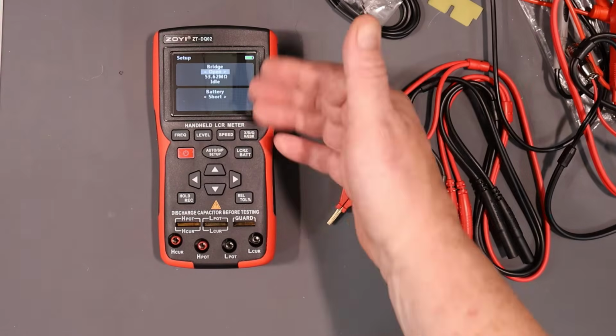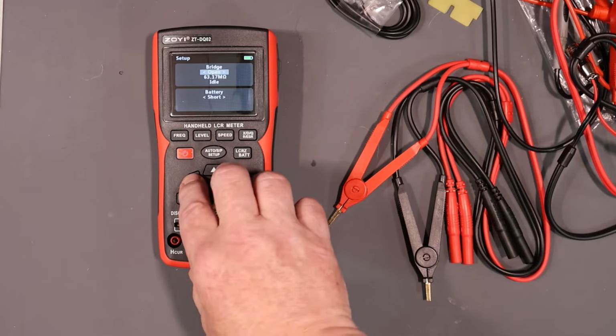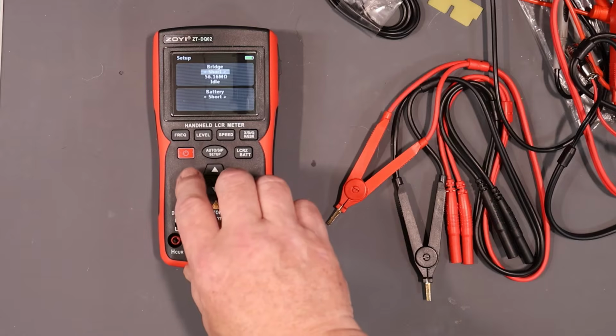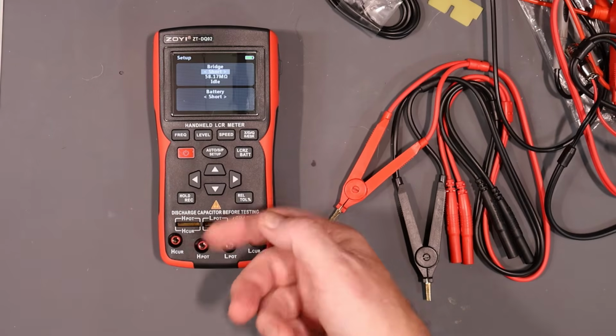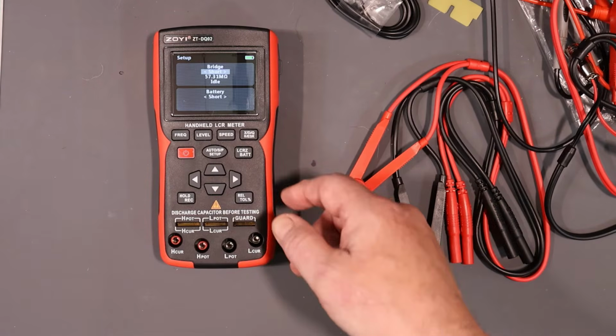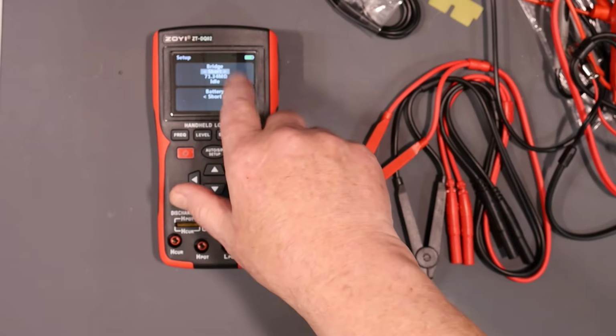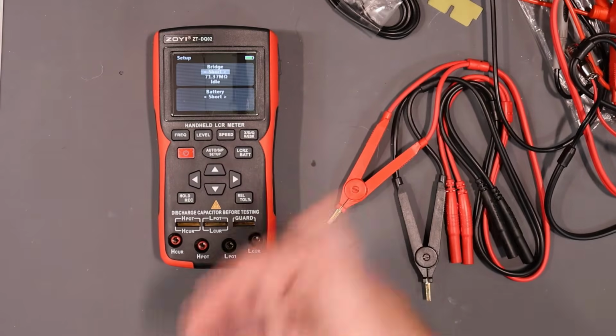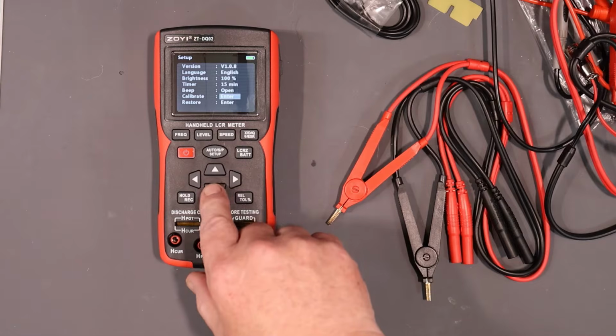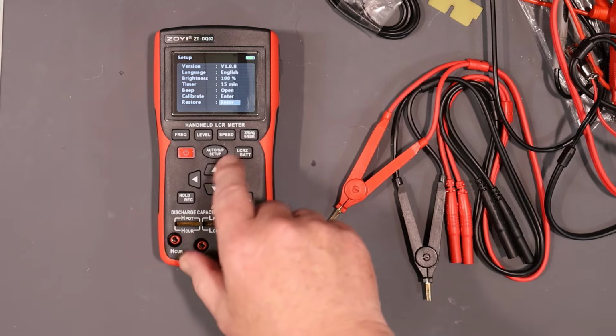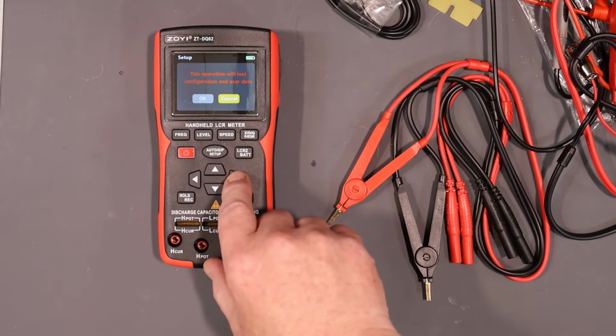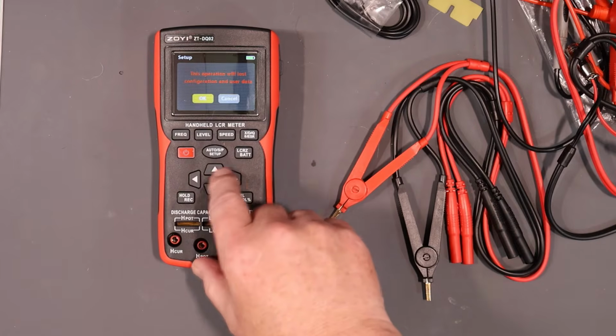As for me, I'm just going to run with the factory calibrations, other than the open and short calibrations, which I'll do when I change my measurement type. Now, if you go in there and start messing around with the calibration and find things aren't working properly anymore, go down here to factory restore and go into that. You can always do the factory restore here.